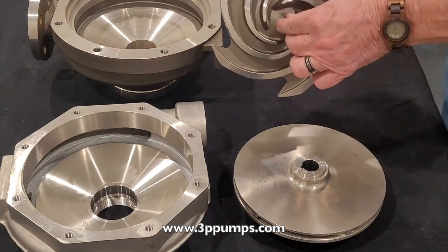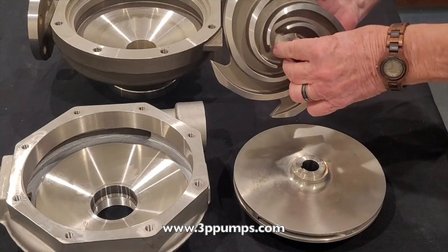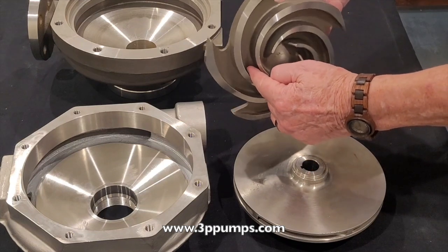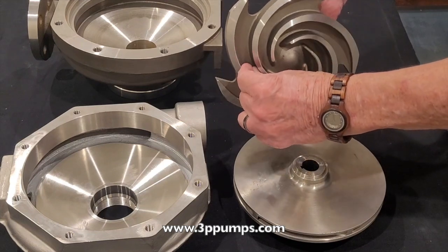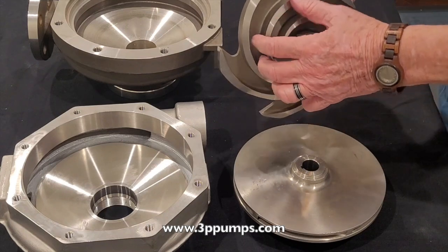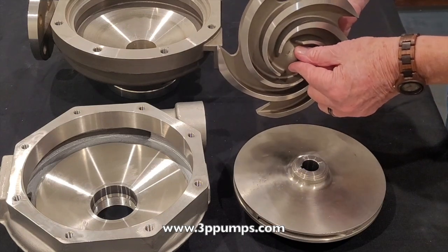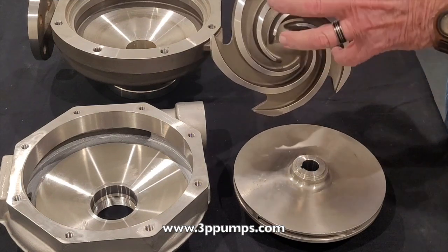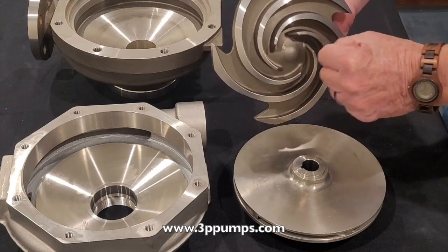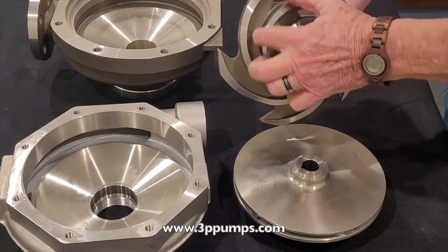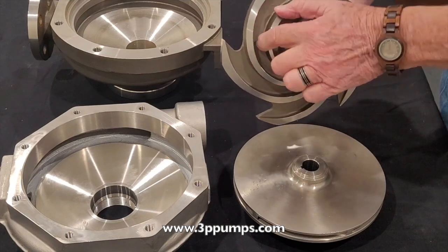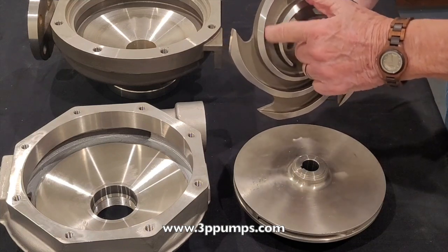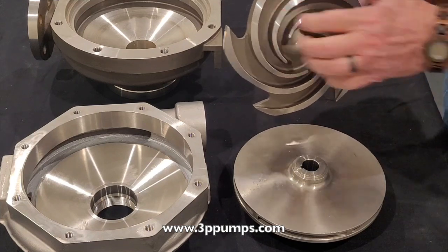Now, when it comes to what we were talking a minute ago, this right here is your eye of your impeller, so this is your low pressure area, and as this water or liquid passes through here, as it gets to this point right in here somewhere, it goes from this low pressure that's right here back to high pressure, and that's when you have your implosion. And it comes back to water, and when it goes back to water, it has all of this volume in here, this gas, and all of a sudden it turns to a little bitty molecule right here. And when it does, it's pulling metal out of here, and it's causing this to vibrate, okay?